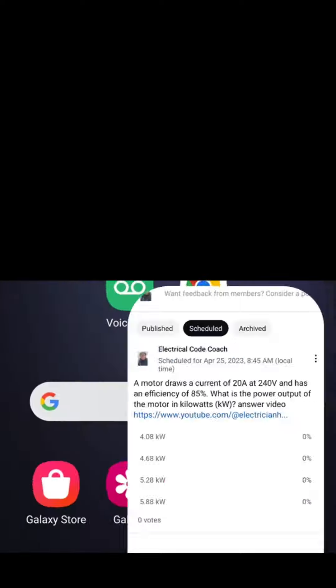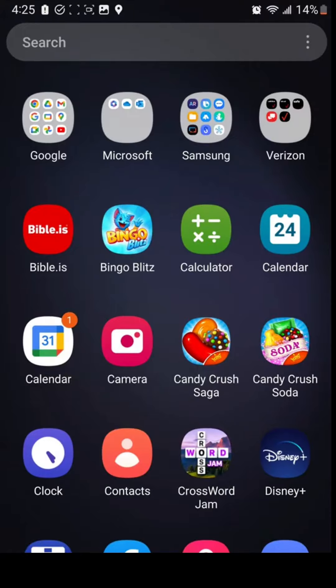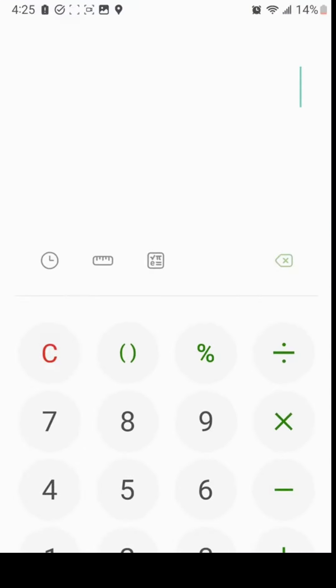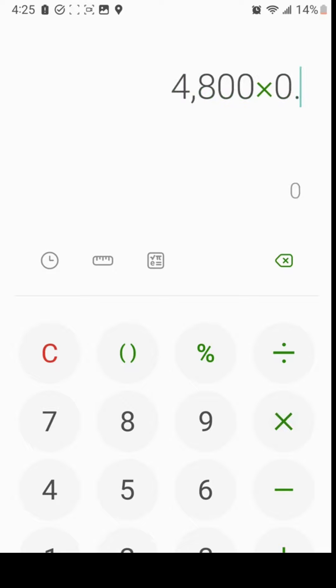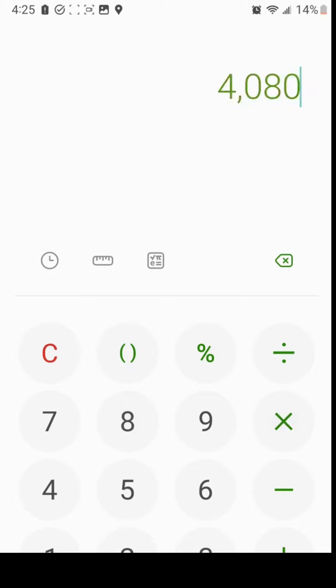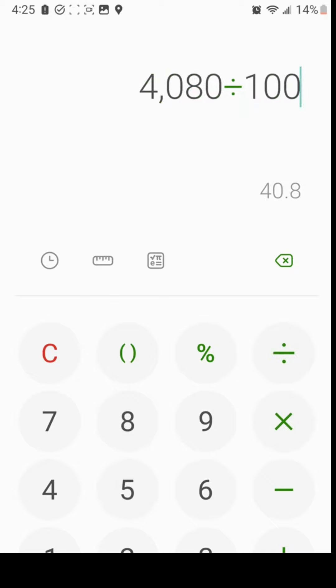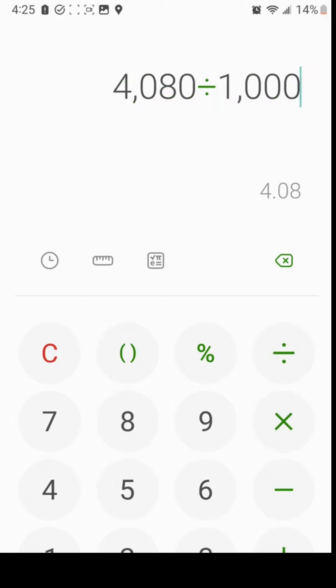So let's go ahead and do that now. Let's get our calculator out. We take our 240 volt motor and multiply it by 20 — that gives us our total wattage. Then we multiply it by the efficiency, and then we divide that by a thousand to get it in kW. And we end up with 4.08 kW.